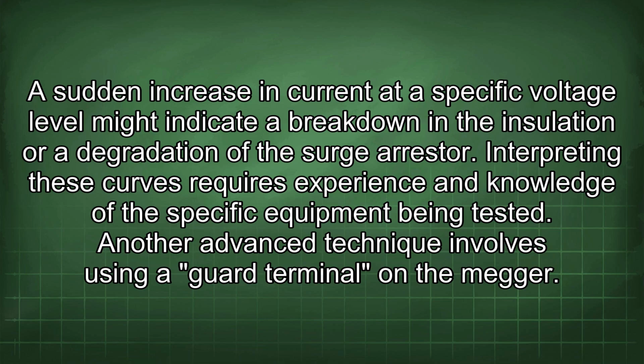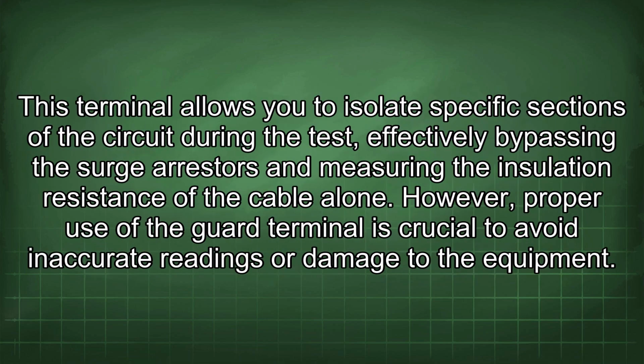A sudden increase in current at a specific voltage level might indicate a breakdown in the insulation or degradation of the surge arrestor. Interpreting these curves requires experience and knowledge of the specific equipment being tested. Another advanced technique involves using a guard terminal on the Megger. This terminal allows you to isolate specific sections of the circuit during the test, effectively bypassing the surge arrestors and measuring the insulation resistance of the cable alone. However, proper use of the guard terminal is crucial to avoid inaccurate readings or damage to the equipment.